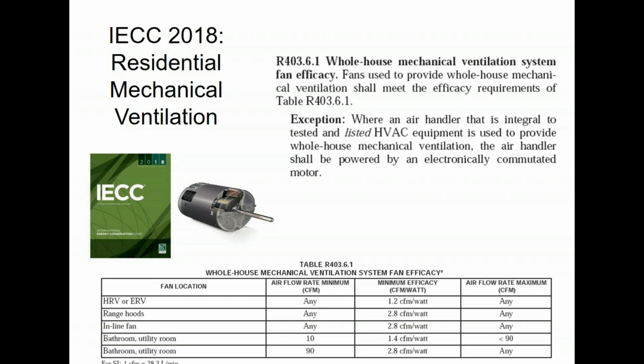If you are going to use an HRV or ERV, do not take the exhaust air out of the return duct of the furnace. When you do that on any project, it'll cost more to operate the ERV than if you've done nothing. It does not save you any energy. You have to take the exhaust air from places that you wanted to throw the air away anyway. So specifically on a residential, you're going to run the exhaust for the ERV from the bathrooms, and then if you need a little bit more, maybe from like a hallway or something like that.